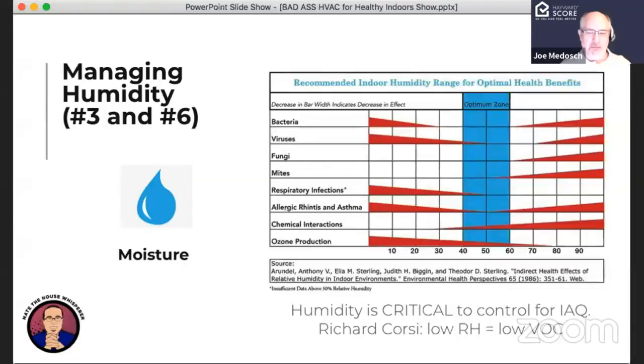I'll bring this chart back up one more time. I have a different philosophy on this chart because ASHRAE had an older version that went down to 30. Where I live it's rare to get that - I'm in a dry climate, in Arizona. I also live in Colorado, and it's rare to have moisture sometimes above 20. I think 30 is a good level to achieve, and above 60 has a variety of challenges.